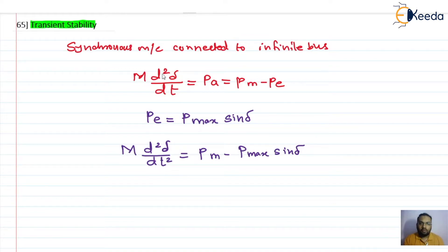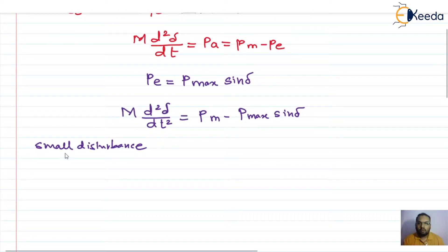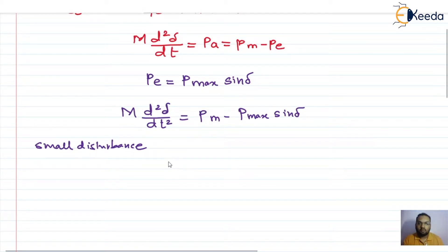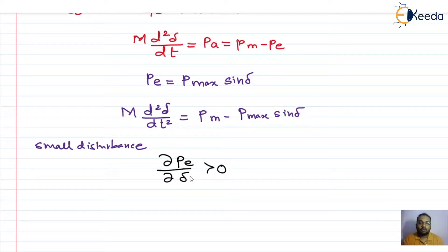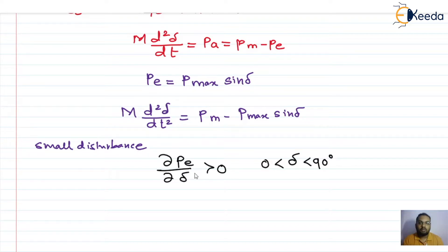When the system is subjected to small disturbances, that is steady state stability studies, we obtained a criteria to check whether the system is stable or not. That criteria is: the differentiation of electrical power with respect to the rotor angle should be positive, and the rotor angle should be greater than zero and less than 90 degrees for the system to have steady state stability.